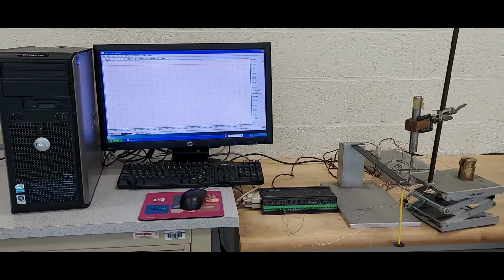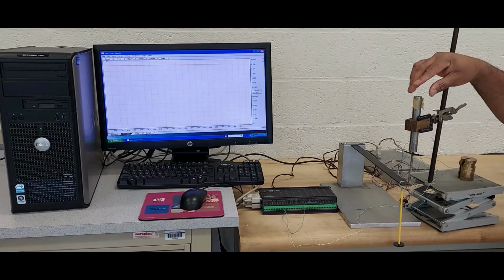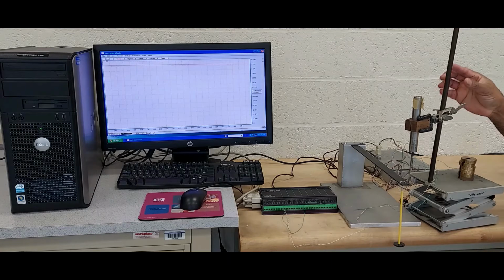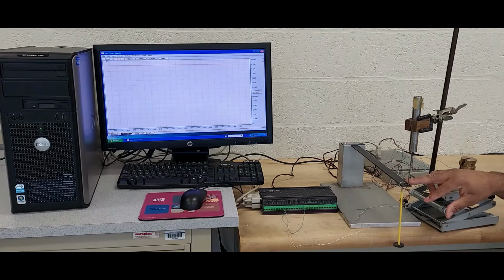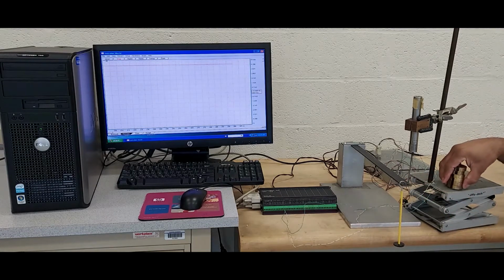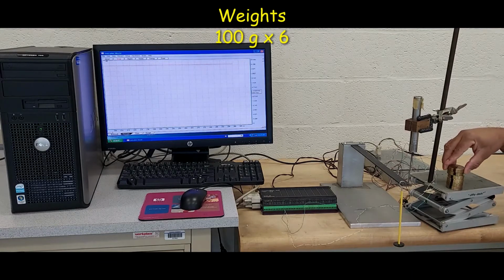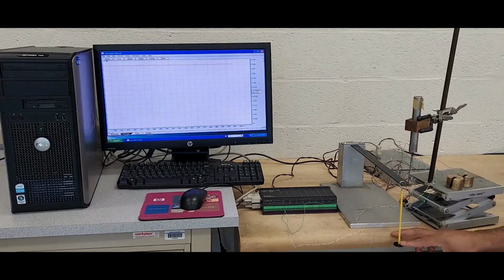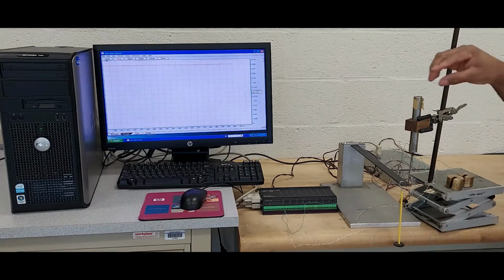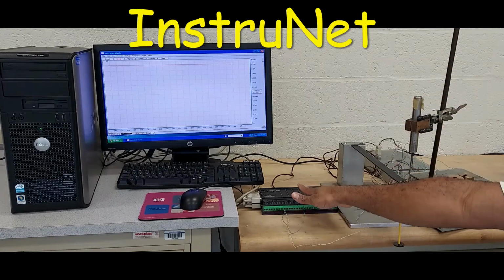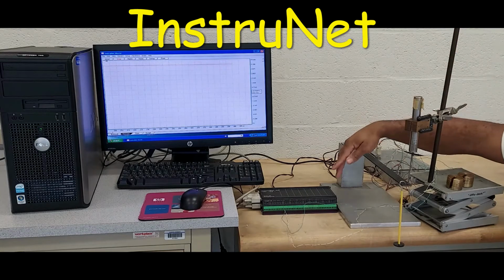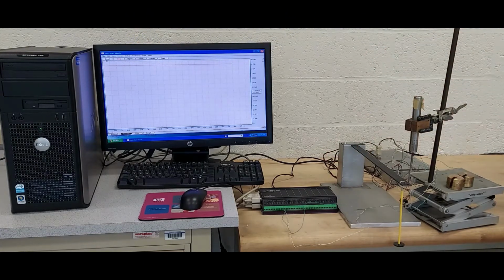To recap the apparatus components, we have our power supply, which supplies voltage to our LVDT, and we have a clamp and stand that keeps our LVDT in place. We have a cantilever beam, and we have weights of 100 grams each, and we have 6 of them, which will be applied to the free end of the cantilever beam. The LVDT is then connected to our InstruNet data acquisition system, and from there the InstruNet is connected to our computer in voltage, and you'll have to use the calibration given previously to calculate your displacement.